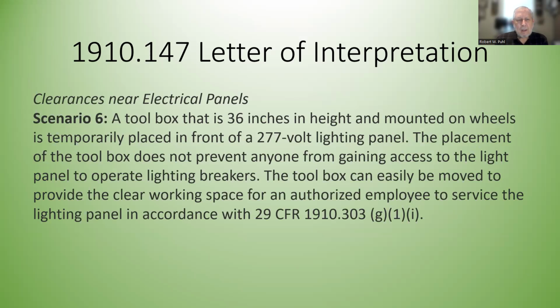So, all right, clearance near electrical panels. Scenario 6, a toolbox that is 36 inches in height and mounted on wheels is temporarily placed in front of a 277-volt lighting panel. The placement of the toolbox does not prevent anyone from gaining access to the light panel to operate lighting breakers. The toolbox can easily be moved to provide the clear working space for an authorized employee to service the lighting panel in accordance with 29 CFR 1910.303(g)(1)(i).